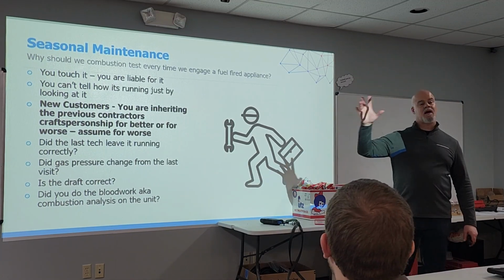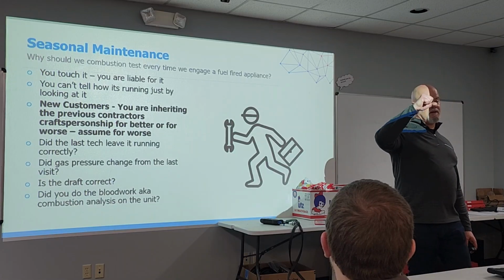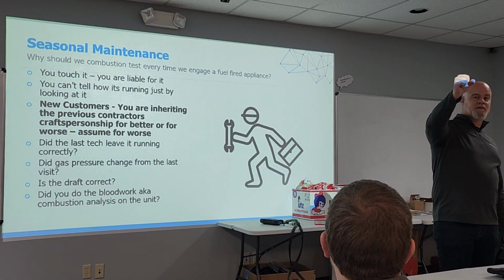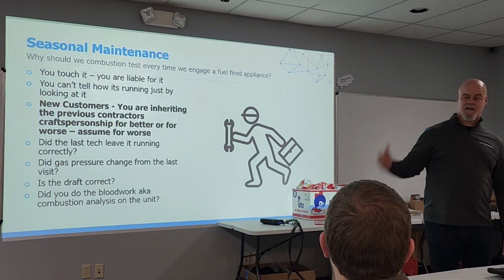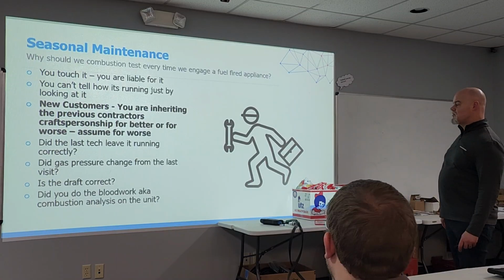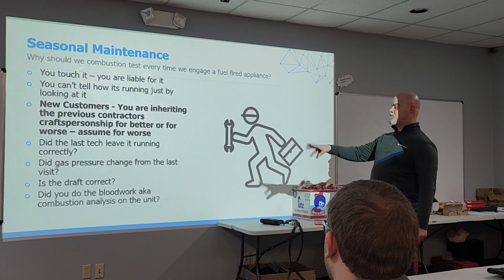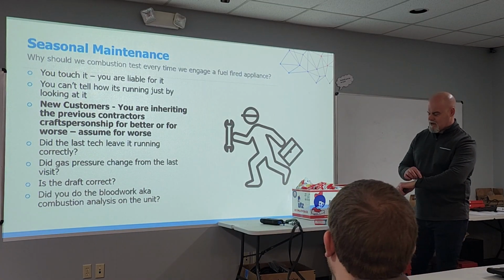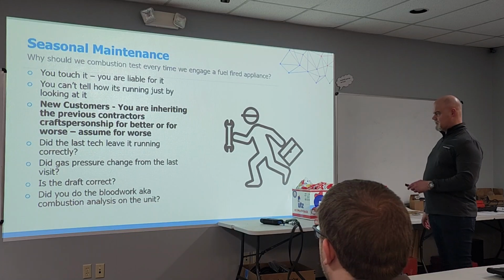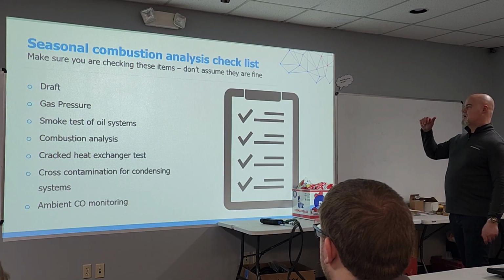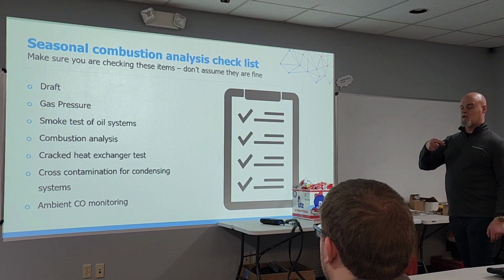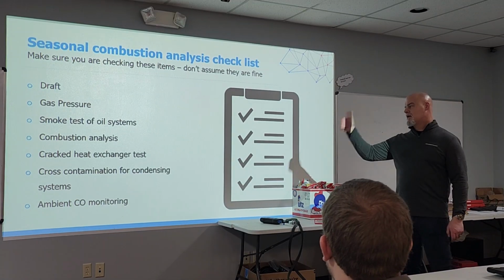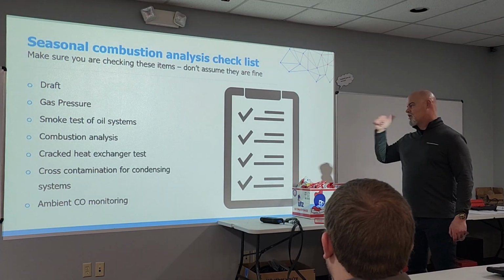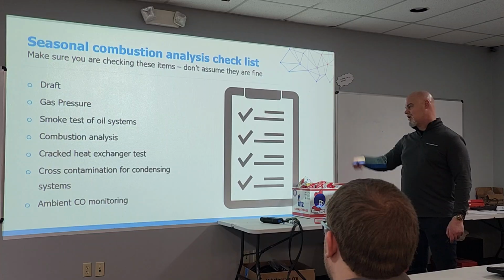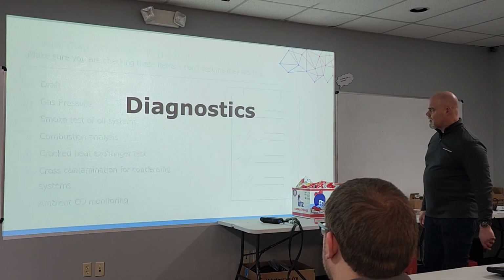You saw that guy in those slides, at the beginning, where it was the pictures of the naughtiness that's taking place up there. You saw the guy on the ladder pulling the stuff out of that exhaust. That's what can happen from visit to visit, okay? And then did you do the blood work on that system, otherwise known as the combustion analysis? Seasonal checklist. Draft, gas pressure. If you're working on oil systems, do a smoke test first, combustion test, cracked heat exchanger, cross-contamination verification, which I'll get to, as well as ambient CO monitoring.